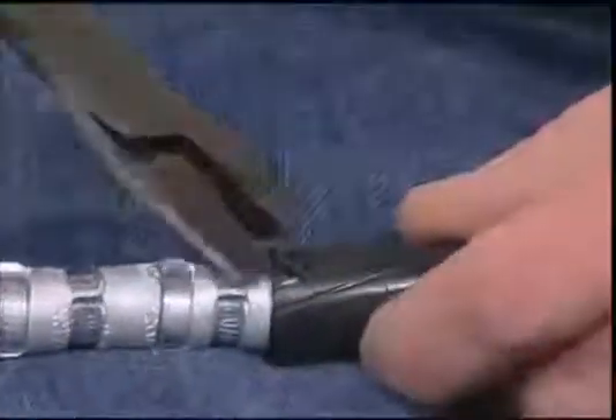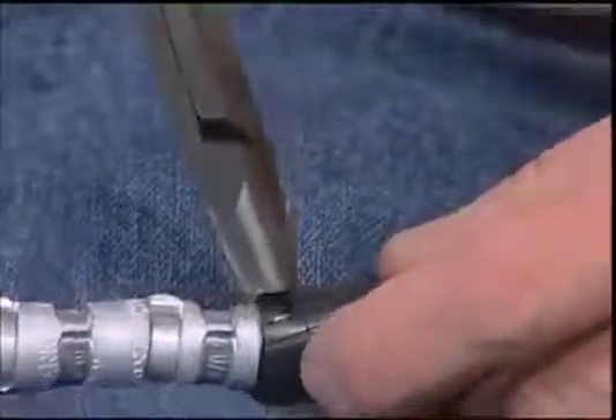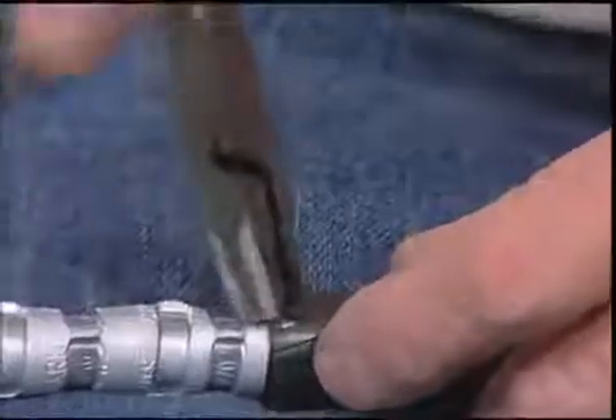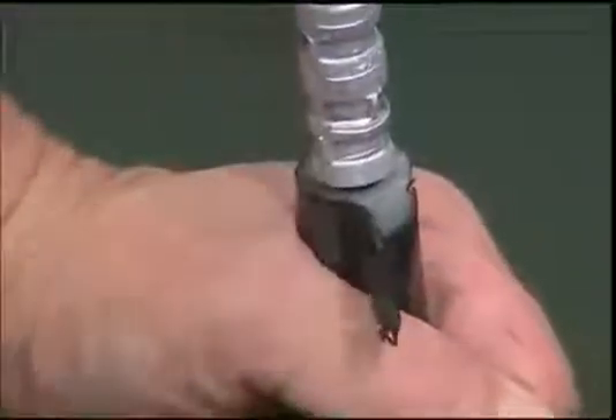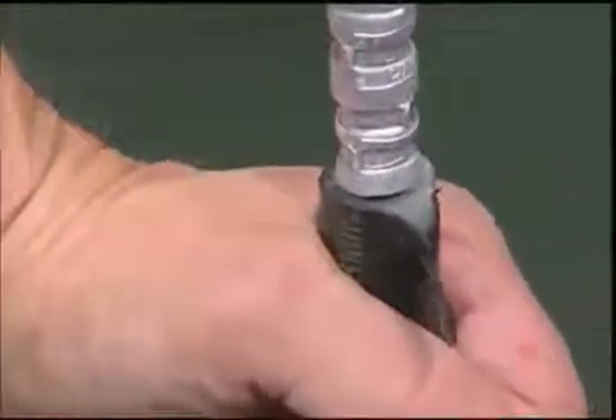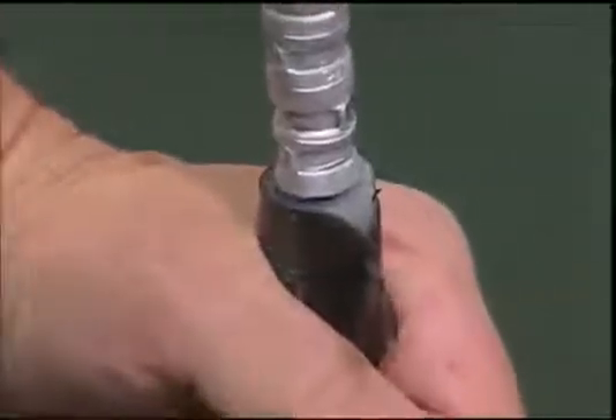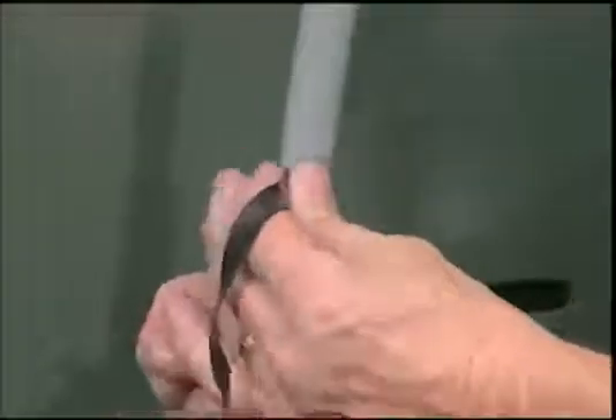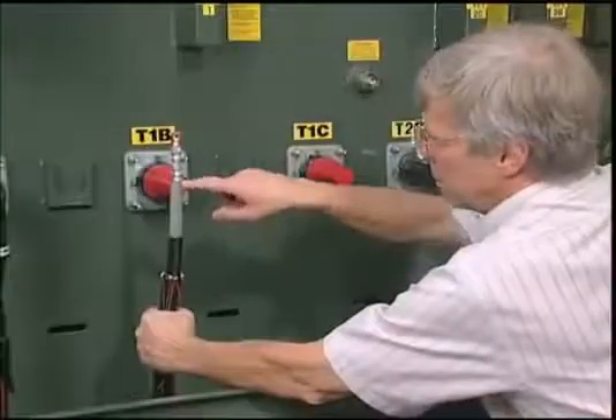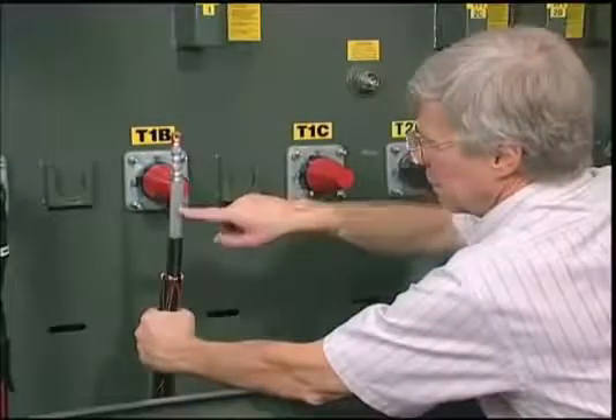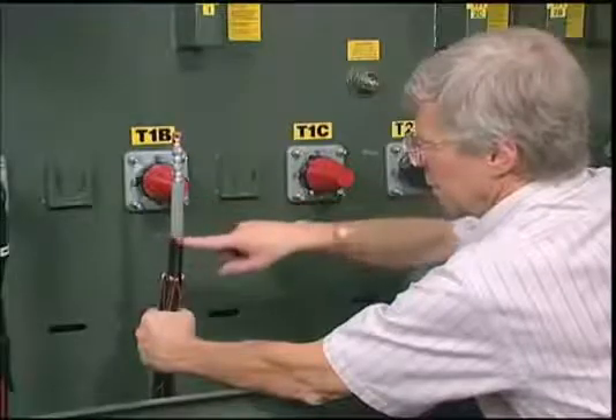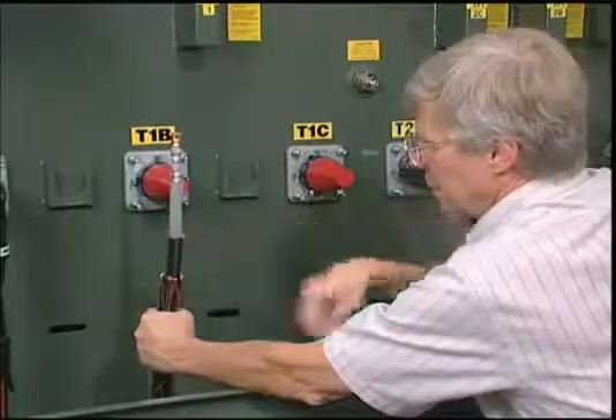Now, using a pair of pliers, slowly and carefully remove the insulation shield. Be sure the end of the cut is straight, perpendicular to the cable. Take care that the insulation is not nicked. Spiral witness lines from the tool are normal. Small nicks in the insulation may be sanded, but any nicks in the insulation at the end of the insulation shield cannot be repaired.